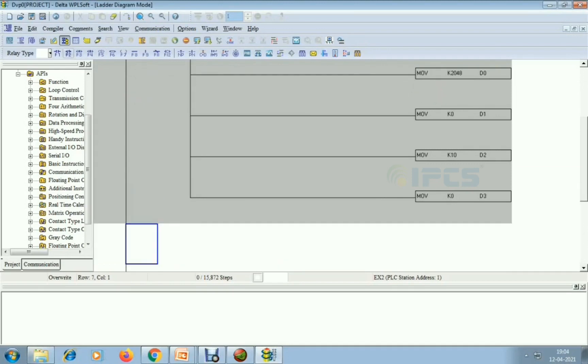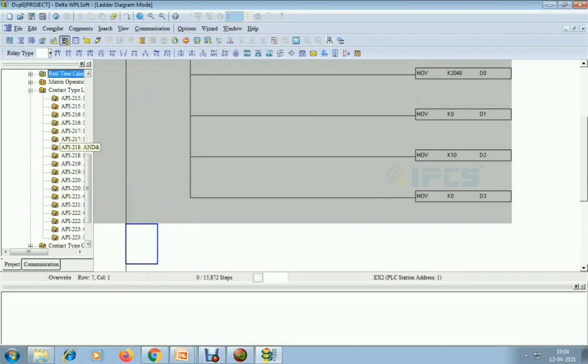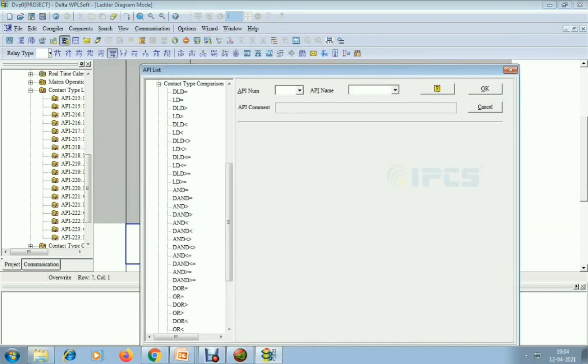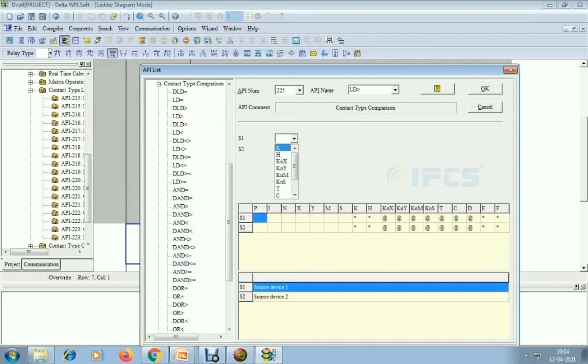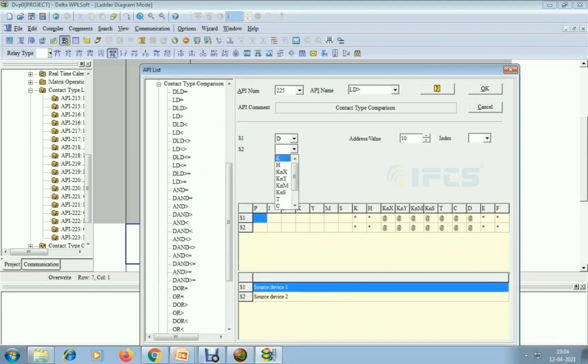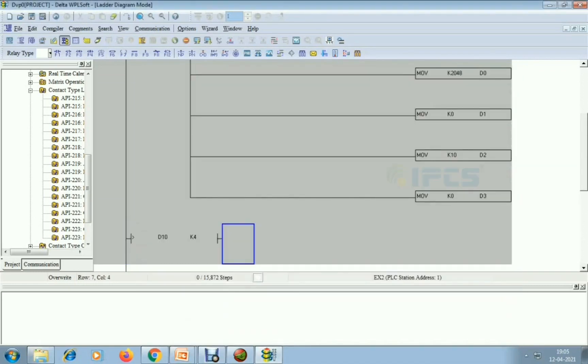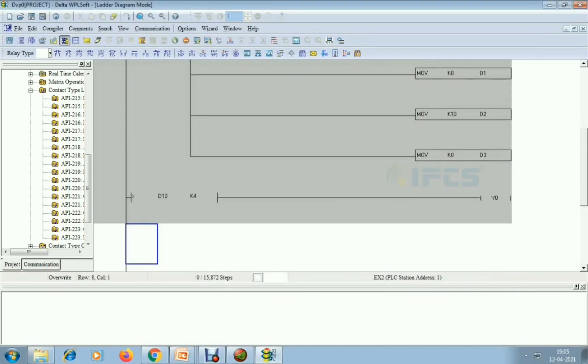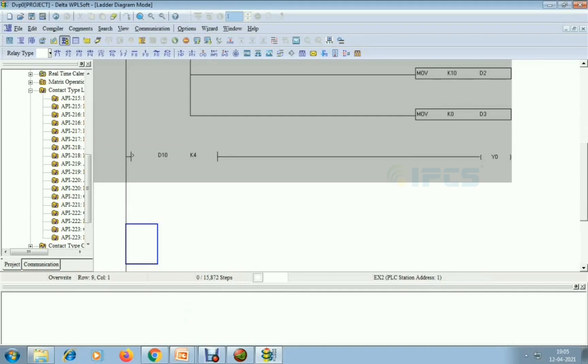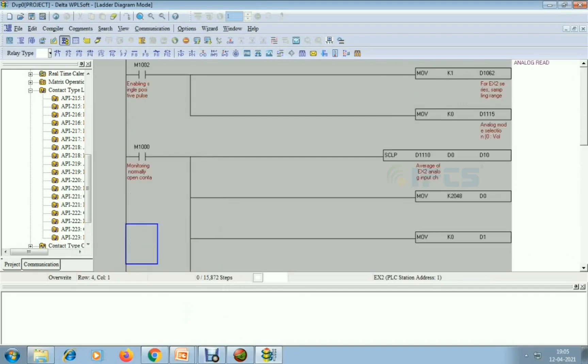Next I am choosing a comparison contact — contact type comparison, greater than LD. I am giving input D10, which is the scaled destination value. If D10 is greater than K4, meaning above 4 volts, then motor output Y0 will be enabled. Now I am compiling the code.